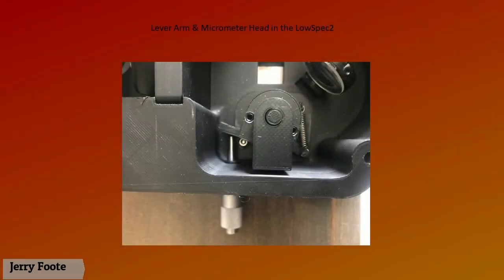One of the issues with this is occasionally with temperature change, we still noticed there was a calibration change. We traced that to an issue in the LowSpec that uses a micrometer and an arm coming off the grating, and of course the housing that it's all mounted to. As the temperature changed, we noticed that micrometer and lever arm allowed the angle of the grating to change, affecting that 6 angstrom shift we saw in the calibration.